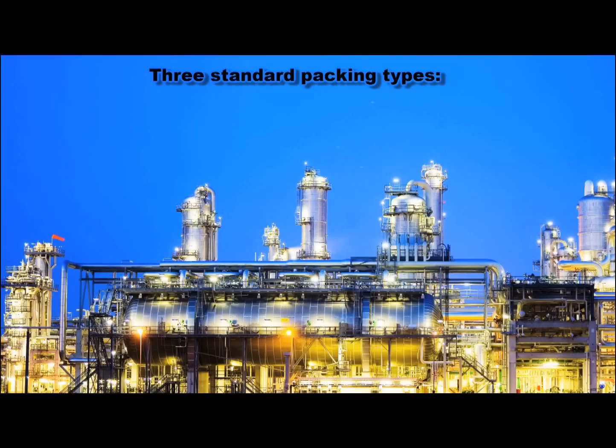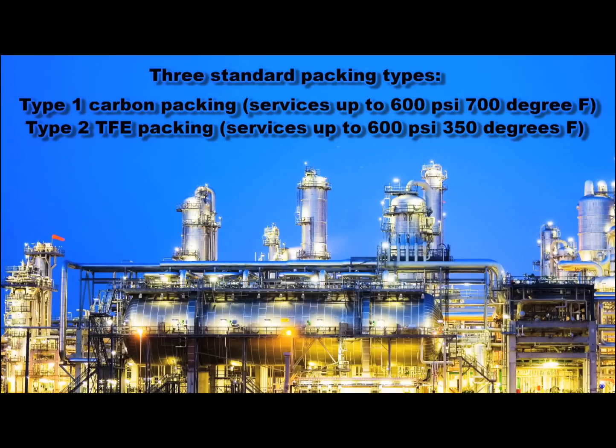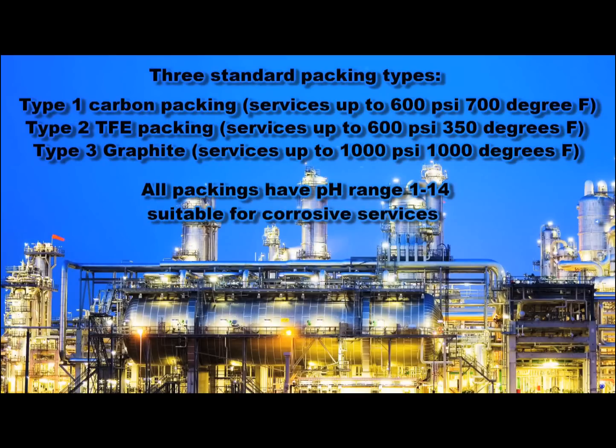Standard packings are also available in three specifications. Type 1, Carbon Graphite, for services up to 600 PSI and 700 degrees Fahrenheit. Type 2, TFE, for corrosive services up to 600 PSI and 350 degrees Fahrenheit. In addition, the highly regarded Type 3, Pure Graphite, for any kind of service up to 1,000 PSI and 1,000 degrees Fahrenheit. All three types are capable of 1 to 14 pH services.